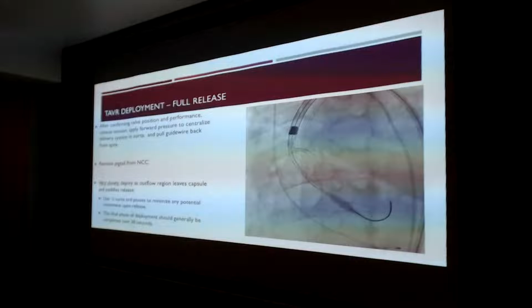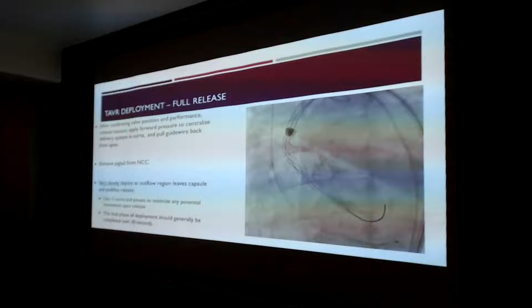Your full release is going to be slow and methodical. I do 15-degree turns. I free up the catheter system, 15 degrees more, free it up, 15 degrees more. This then controls your pace of actually releasing these tabs. The slower you go, the better. It allows for the valve to really sink in the annular plane. You'll get no vertical movement on tab release. And this is really how slow it is.